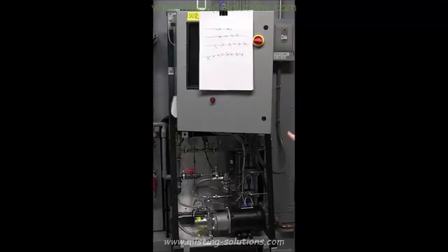And you can't just let that high pressure sit there, it will slowly bleed off. So these two solenoids, one's normally open, one's normally closed. When you energize it, the one that goes out to a zone turns on, the dump valve closes off. As soon as you de-energize both of them, the one that goes out to the zone turns off and the dump valve turns on, and it takes the high pressure water, I'm going to say 1,000 psi, that's max, and kind of dumps it to drain.